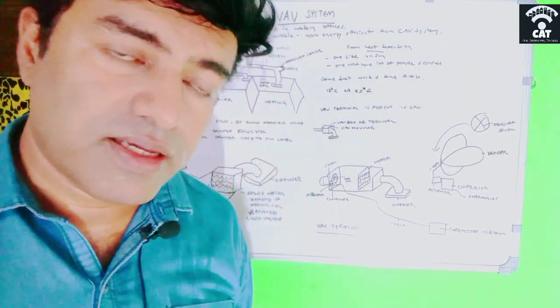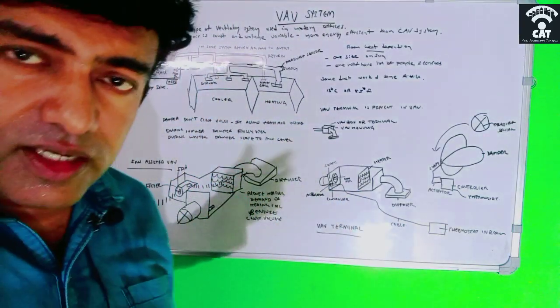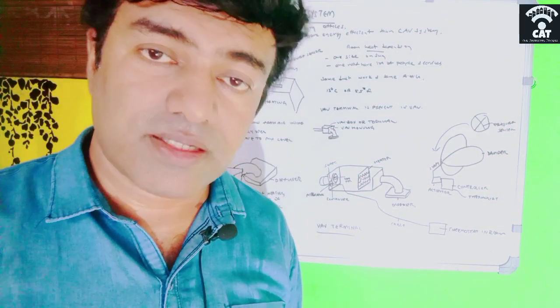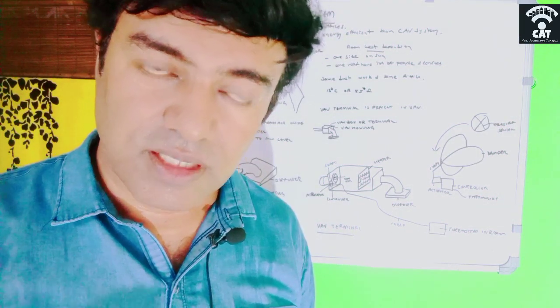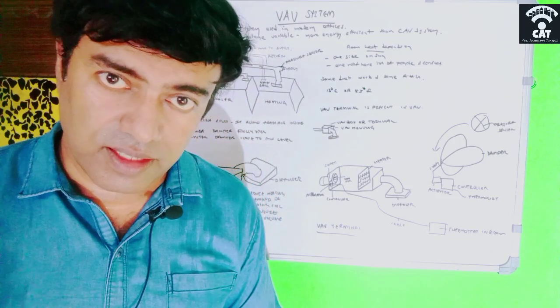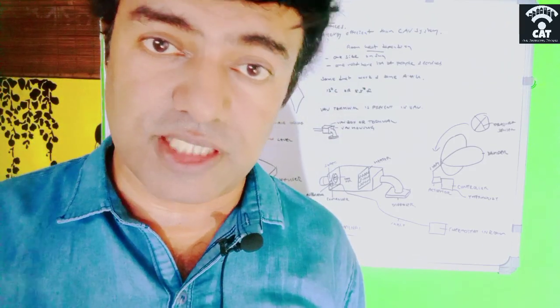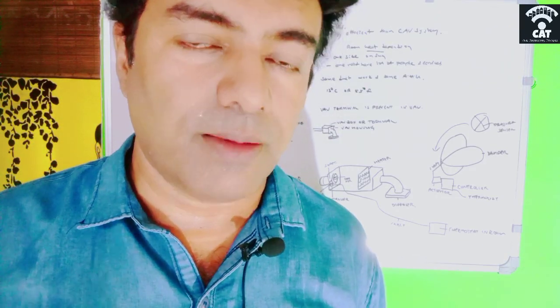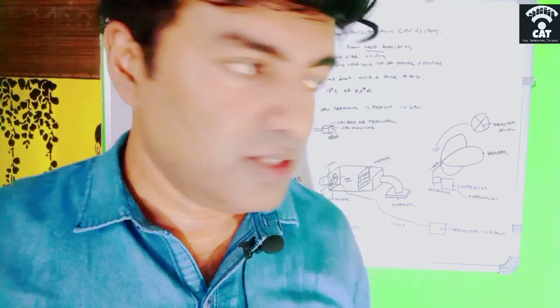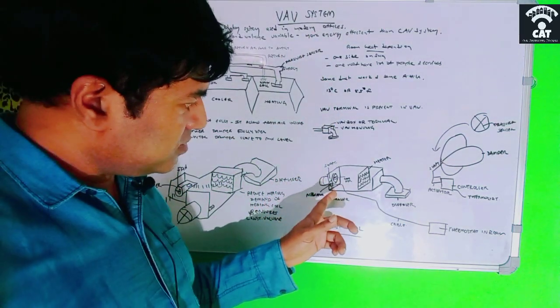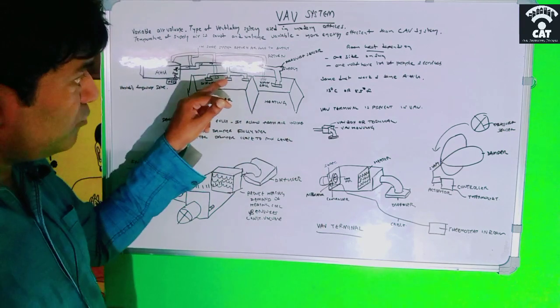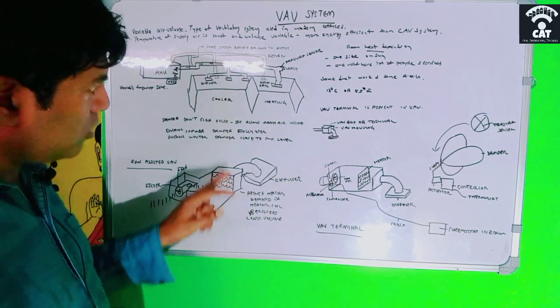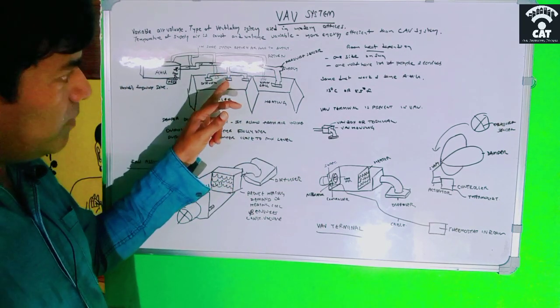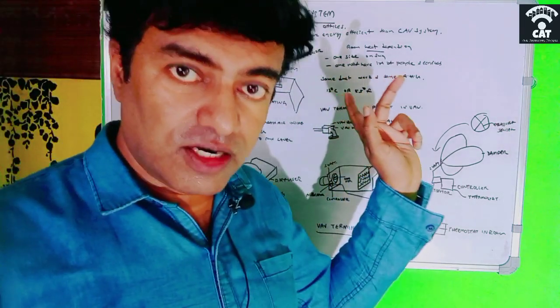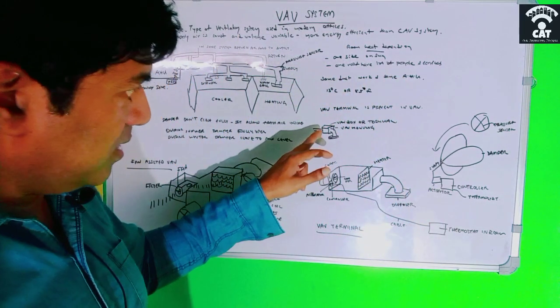So let us see the difference. What makes the VAV system a VAV system is that it has a VAV terminal, that is, a variable air volume terminal, which is absent in the CAV system, the constant air volume system. This is called the VAV system. Before the diffuser there is a small box-like thing. Here I didn't show it, but before the diffuser, inside the false ceiling, there is a box-like thing like this.